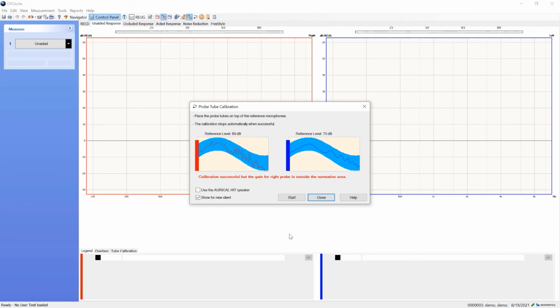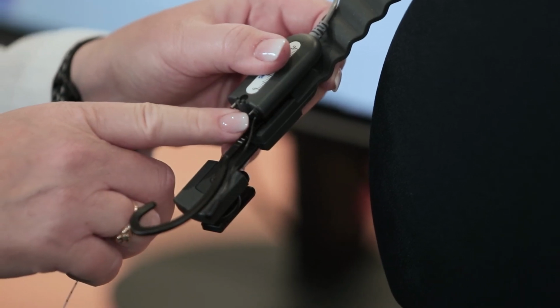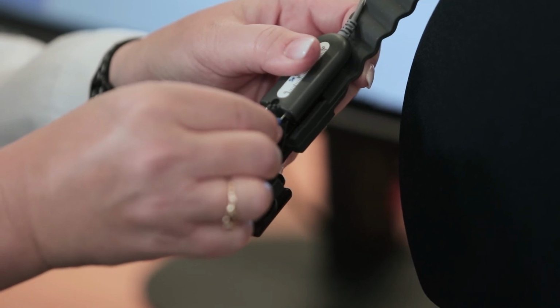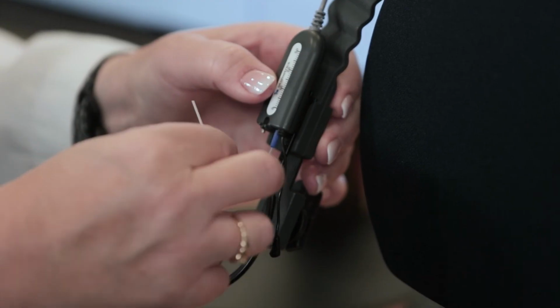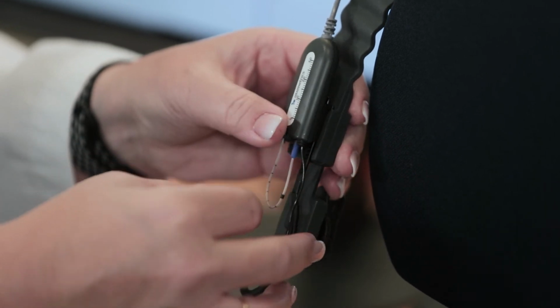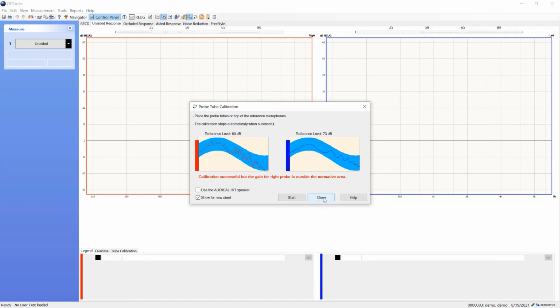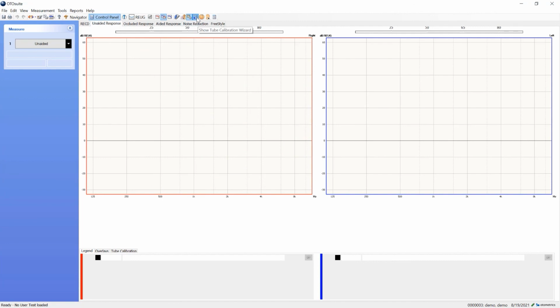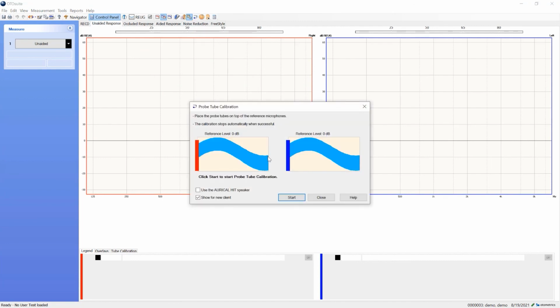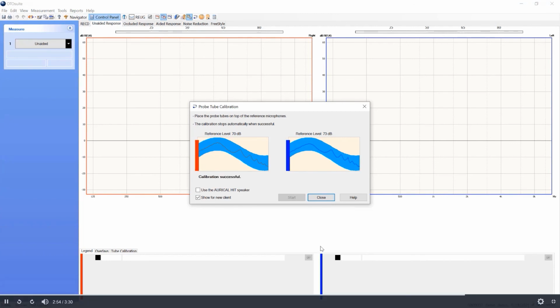In this example, the software indicates a problem with gain for the right probe. When calibration is not successful, you might try replacing the probe tubes, straightening the tubes, and/or ensuring the probe tubes are connected correctly and not touching other objects. You should also check the connection of the probe to the free fit collar to ensure it's securely connected. In this troubleshooting example, the probe was not securely connected to the free fit collar. We'll repeat this calibration. This time, calibration is successful.